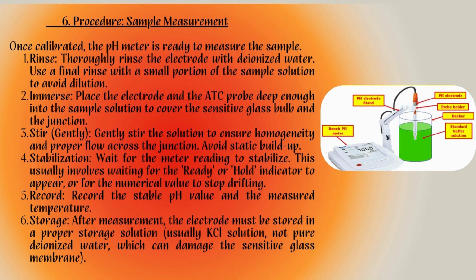The second step is immerse and stir. Place the electrode and ATC probe deep enough into the sample. Gently stir the solution to ensure homogeneity and proper sample flow near the junction. Do not stir vigorously. Then the third step is stabilization. Wait patiently. You must allow time for the electrical potential to stabilize. Look for the ready indicator on the meter or wait until the number stops drifting, and then record the stable pH value and temperature.